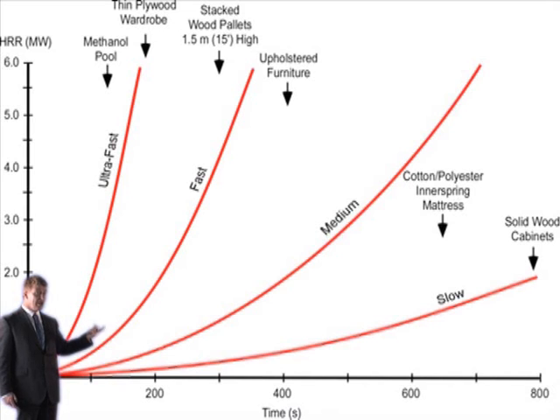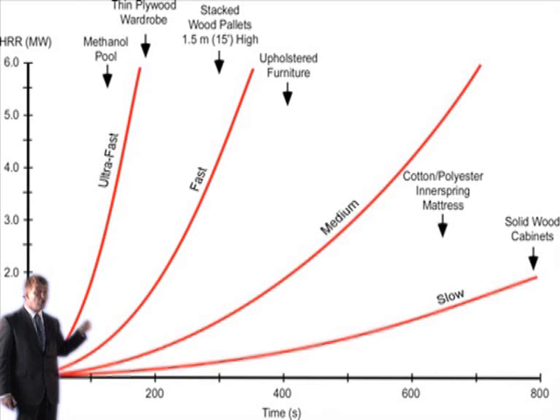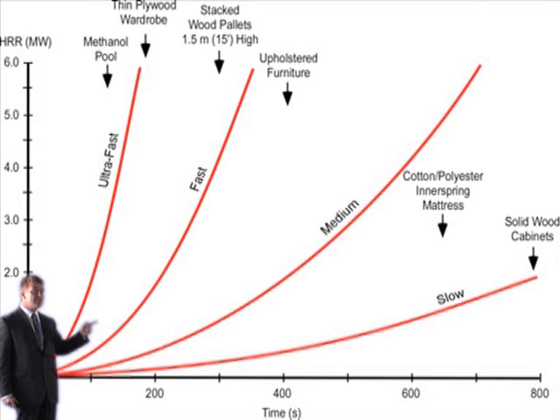This chart shows the heat release rate against time for some materials. For example, a solid wooden cabinet will burn with a slow growth rate, upholstered furniture will burn with a fast fire growth rate, and thin plywood wardrobes burn with an ultra fast fire growth rate. There comes a point in the growth phase at which a certain temperature is reached — normally approximately 600 degrees — at which the whole room becomes involved, and this is a flashover.